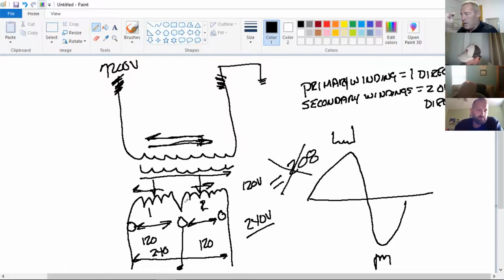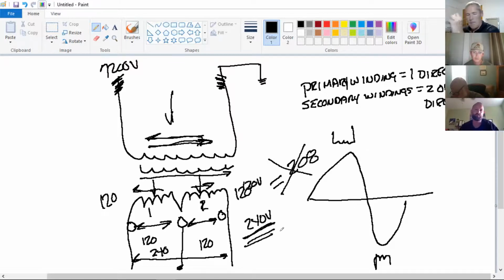This is going north and south all the time on the primary winding up top. So at that point in time, I'm able to produce 120 and 120, not at the exact same time, but close enough to produce 240. In essence, how many times per second am I at zero? 120 times per second - that's fast enough and captures enough. This is where you get 240 volts.